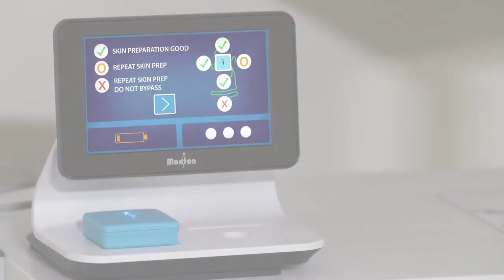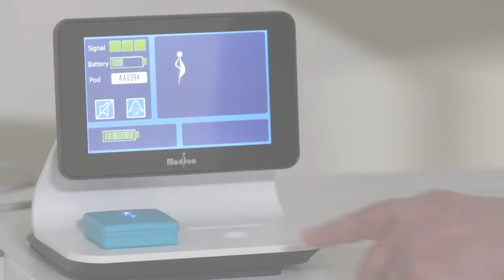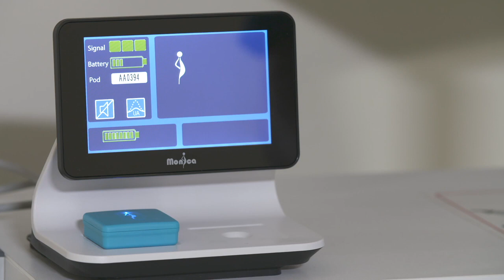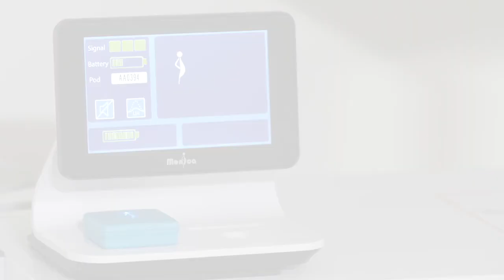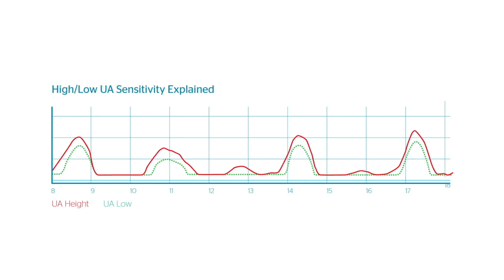High UA sensitivity is the default startup condition when monitoring commences, and is the correct setting for established labor. In pre-labor, the UA trace can look hypersensitive due to small deflections. Using the low sensitivity setting will decrease the UA amplitude, suppressing unwanted low amplitude UA, but as shown in the diagram, it will also reduce the contraction duration. For this reason, when you select low UA sensitivity, it will automatically switch back to the high setting after 60 minutes. By looking at the UA trace, the Monica identifier spike is reduced in height by 50% when the low UA sensitivity setting is selected.